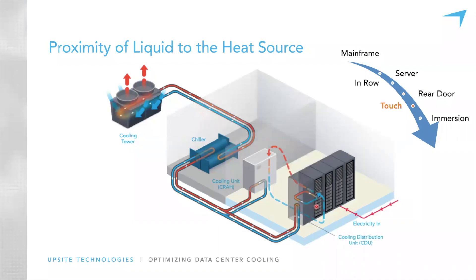This is the first time that we get liquid back to the source. With direct liquid or touch cooling, we have either a row-based or rack-mounted cooling distribution unit — a liquid-to-liquid heat exchanger that transfers heat picked up from the IT components by liquid to another liquid used to carry it out of the building. Liquid now flows through each of the components in the cabinets, picking up heat from the source and transferring it to another liquid.